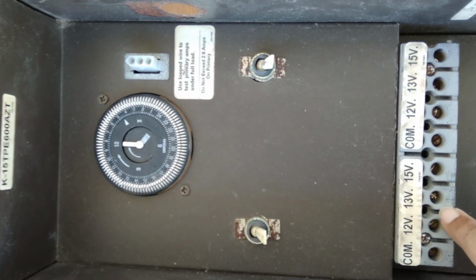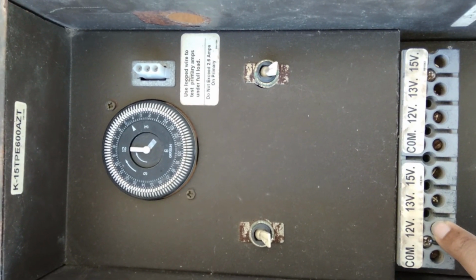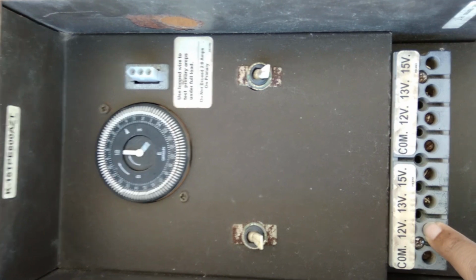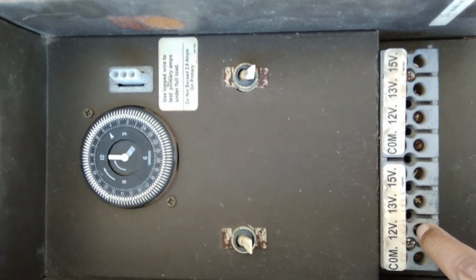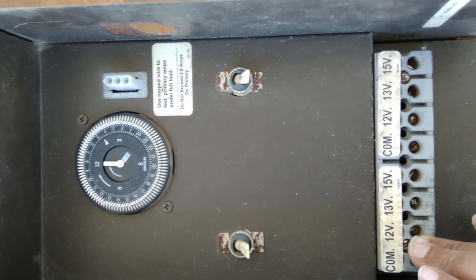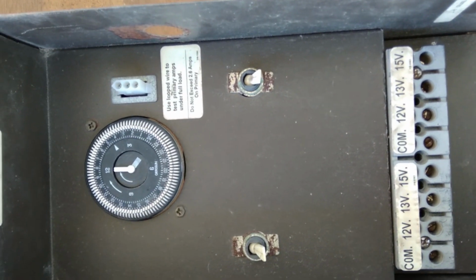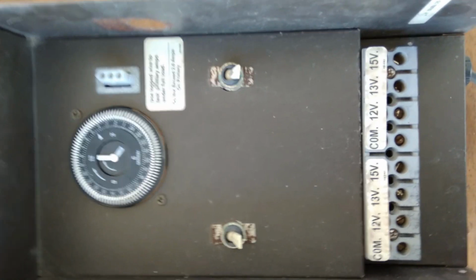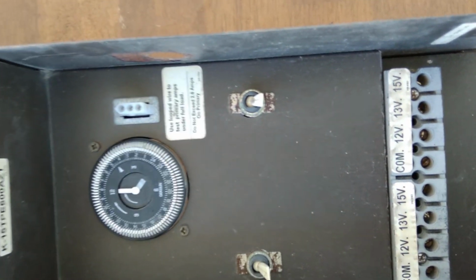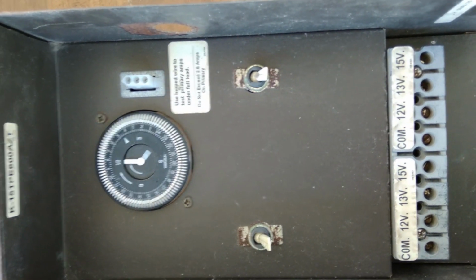Let's say we were to do 12. That's 8 amps per 100. So yeah, that's 24 amps. I don't know, probably 25 amps on this. So yeah, quite significant. The voltage drop goes as you go, and landscape lighting tends to be very far, sometimes a couple 100 feet.